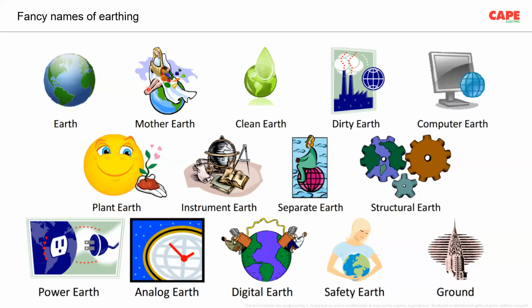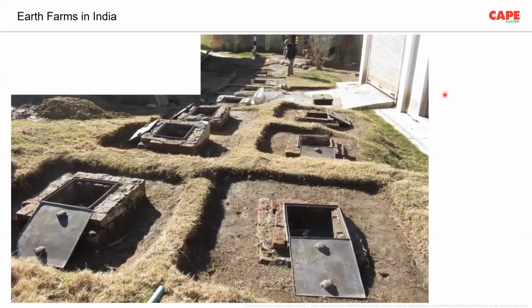People started coming out with different earth electrodes. I have clean earth, computer earth, digital earth, analog earth; all these different names came into existence in India because of these two particular pictures. People thought these were innovations of the earth electrode. Unfortunately, wrong innovations. The second part is the earth farm. There are places where so many earth pits are made separately. Each one is for a typical application: two for DG neutral, two for DG body, two for transformer neutral, two for transformer body, and all these things. I call this a useless earth farm.